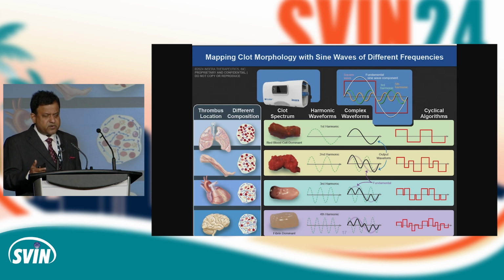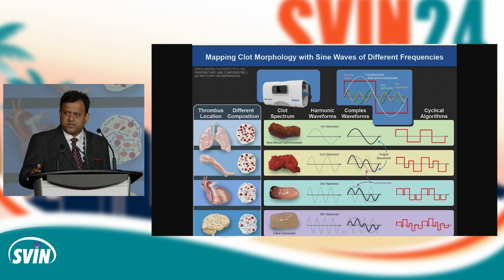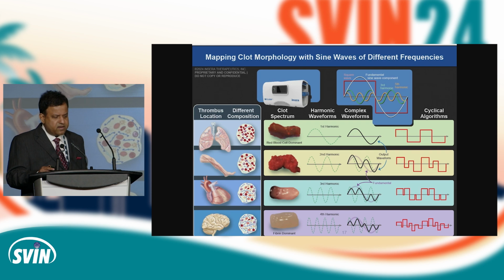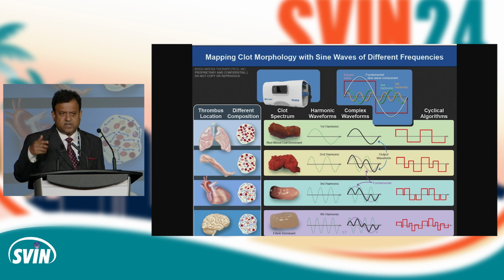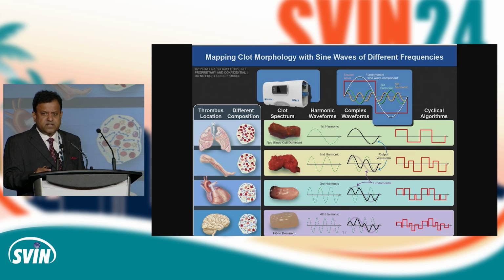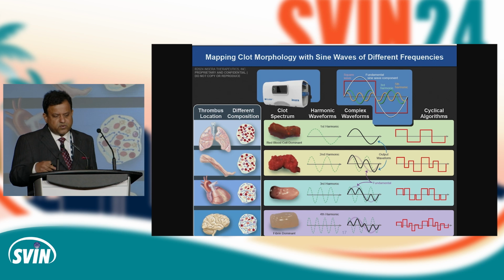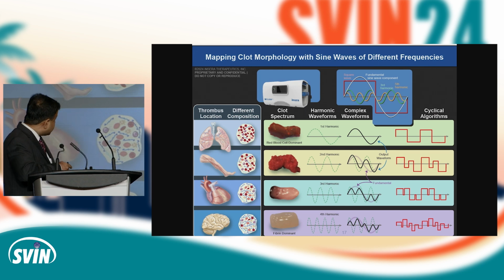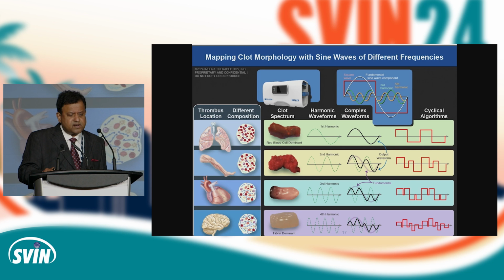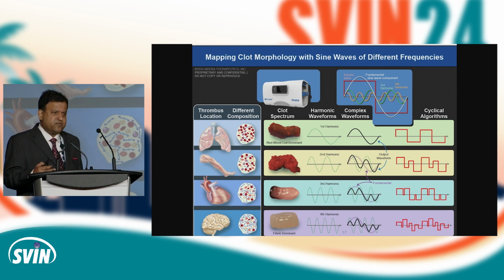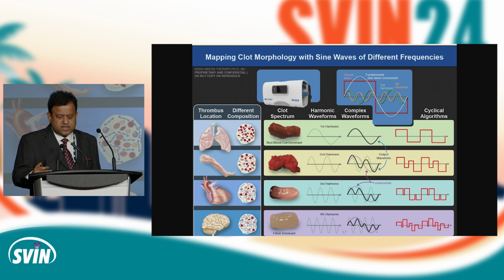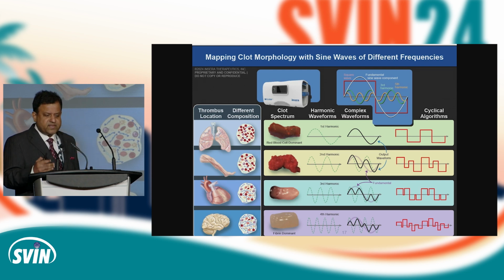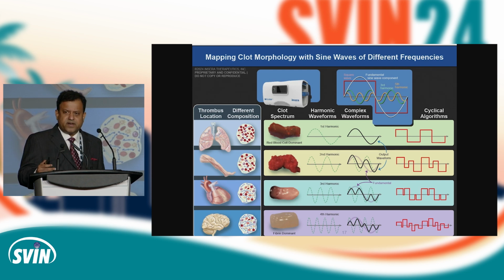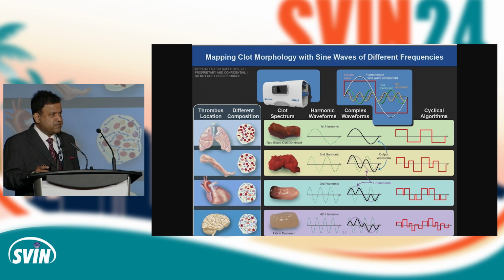Now, how does cyclical aspiration actually work better than continuous uniform aspiration? I just want to take a minute on this slide. You see there are different clot types in different locations of the body, varying from RBC to fibrin and a mixed composition. What we started off with is a simple waveform that is the first harmonic for an RBC clot. And we realized that as there is more fibrin composition, you need to change this harmonic. So you get the second harmonic, third harmonic, and fourth harmonic. And this then translates into a square wave approximation that generates these cyclical algorithms.